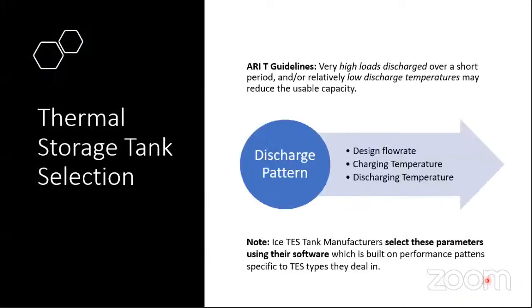Now, once we have the thermal storage capacity, once we have the discharge pattern, before starting anything else, there is a guideline. There is an ARI guideline for cool thermal energy storage, according to which very high load discharge over a short period of time or relatively low discharge temperatures may reduce the usable capacity. When we are talking ice, see, if it was water, I could discharge all of it in whatever time I wanted.